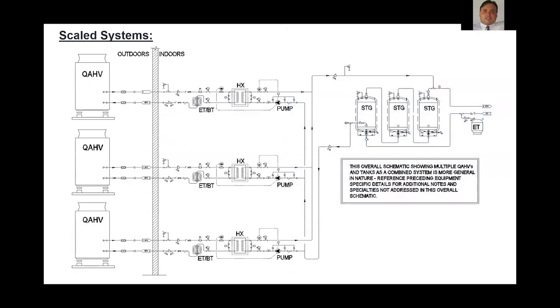And so with our system, obviously this may look different depending on the manufacturer. That scalability exists. We only have a single size heat pump water heater, but again, it's scalable. For each heat pump water heater, you're going to have to repeat that scope of work for the primary to secondary heat exchange. So the heat exchanger, all that closed loop accessory components, the controls, and that secondary side pump with all the temperature controls, you're just repeating that.